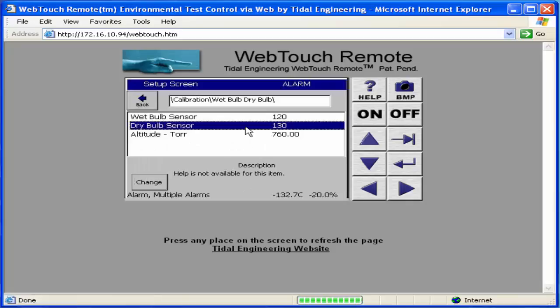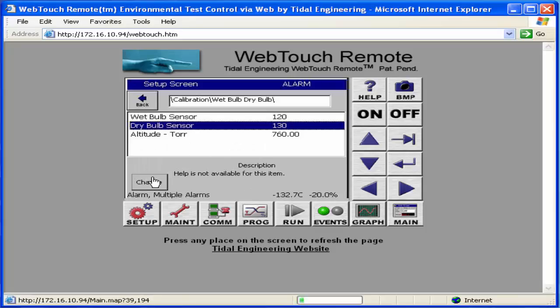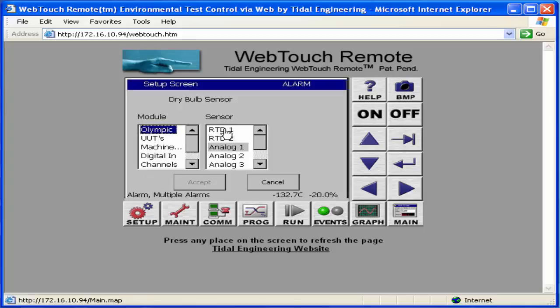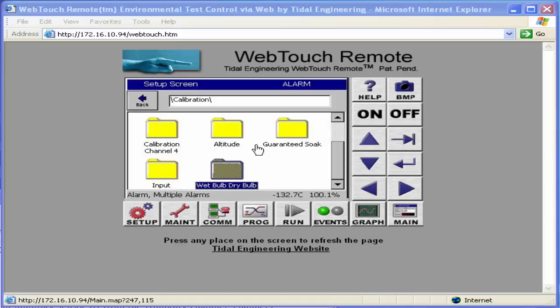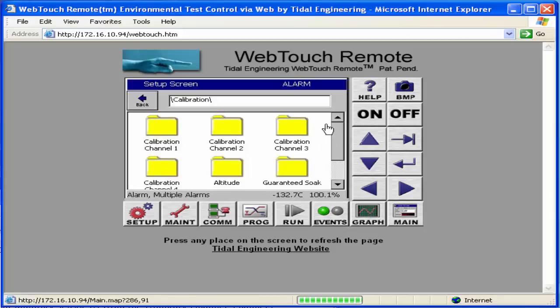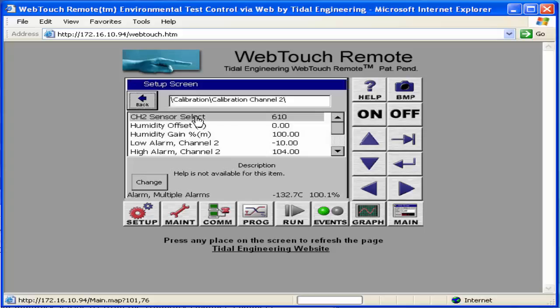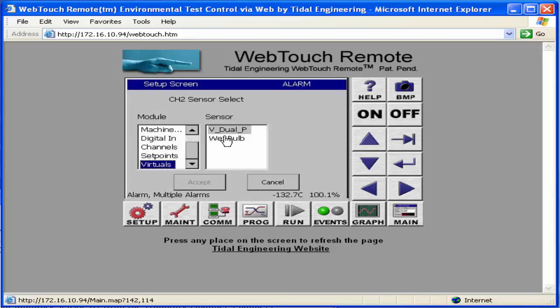Next, I select the dry bulb sensor ID and click Change. I select the RTD1 sensor in the sensor list and click Accept. Last, I scroll up to the humidity channel, calibration channel 2, and assign the virtual wet bulb dry bulb sensor to the humidity channel. I click Change and select the wet bulb sensor in the Virtuals module, and click Accept.